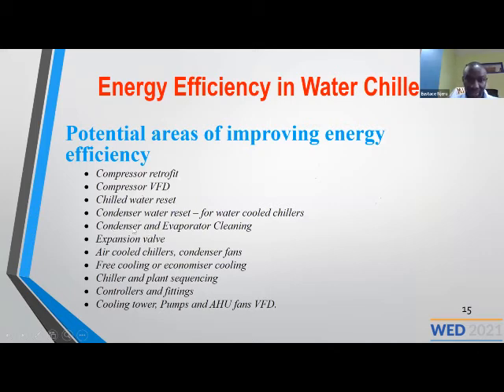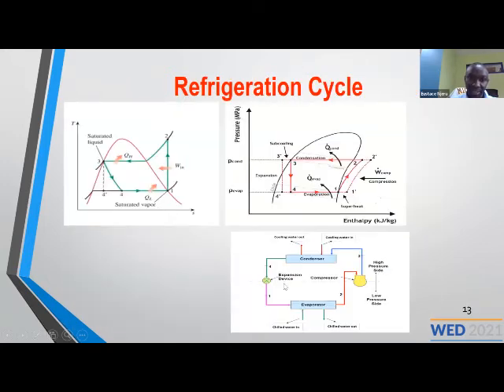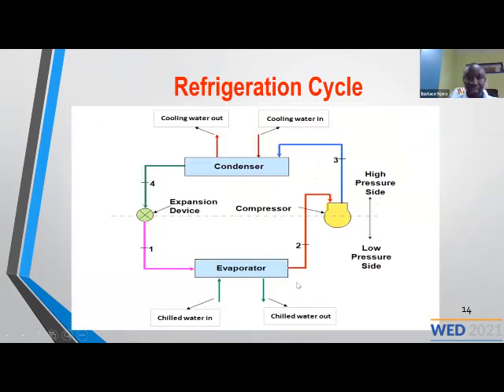The other one is condenser and evaporator cleaning. The efficiency of the refrigeration cycle of the chiller will depend on the efficiency of heat transfer in the evaporators and the condensers. You see here you are cooling water using a refrigerant. So the efficiency of the heat transfer in either of the two will determine the efficiency of the compressor. That will reduce the number of times the compressor is running.